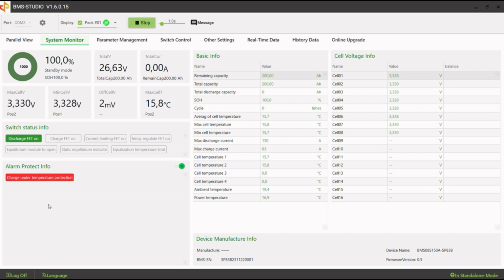Did you spot my mistake? I set the charge under-temperature recovery to 18, but told the BMS to stop charging at 17 degrees. So the cells will never reach 18 degrees, and the BMS will never recover from the charge under-temperature protection.